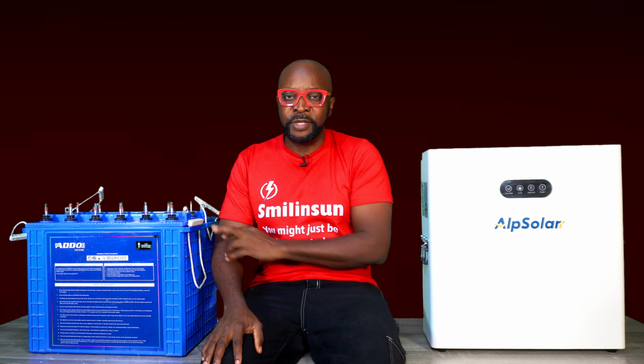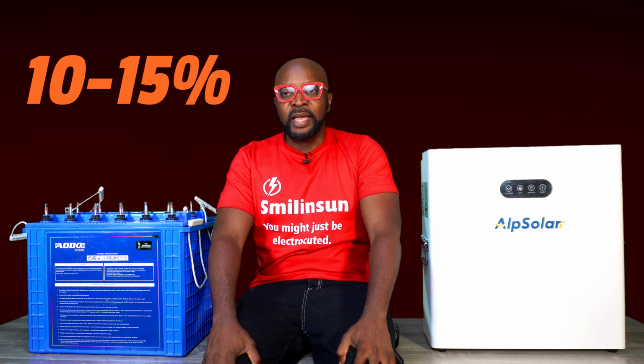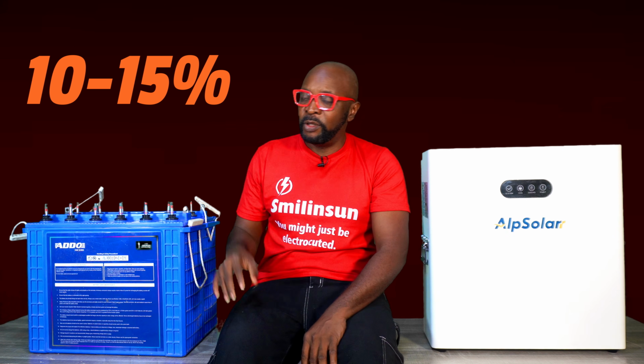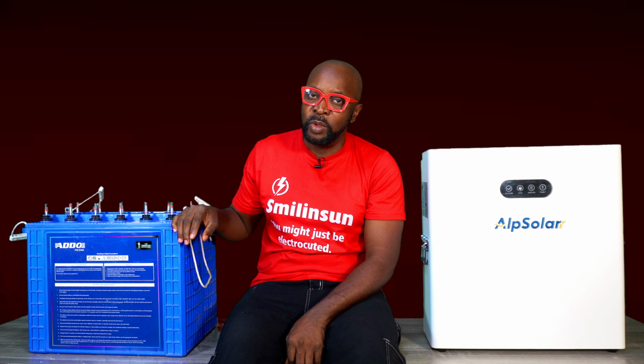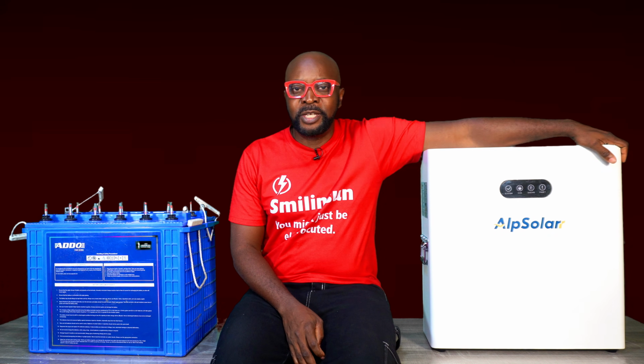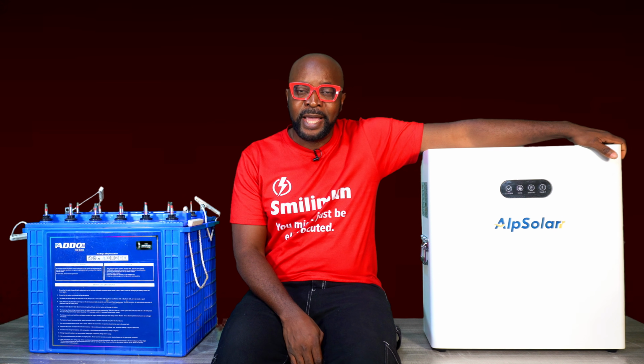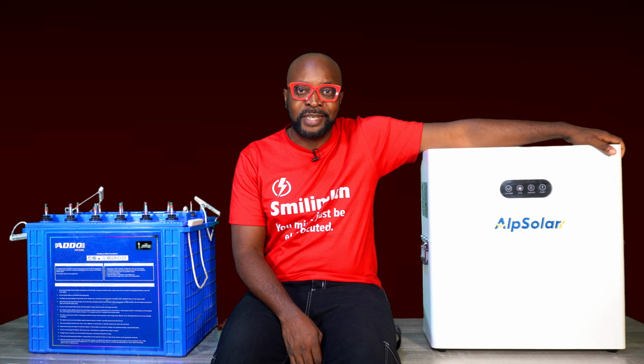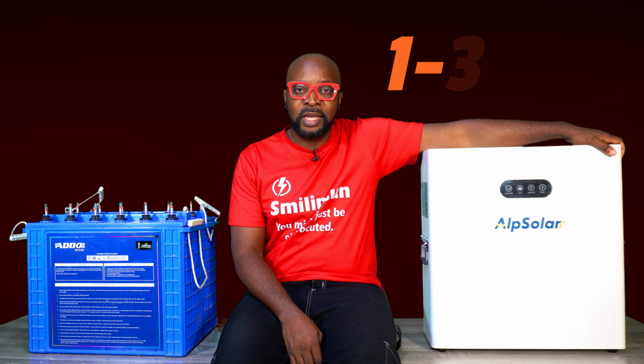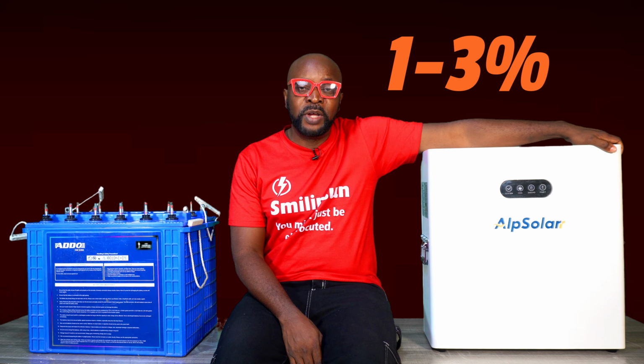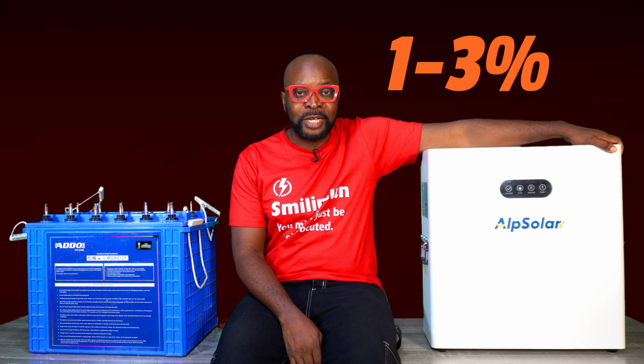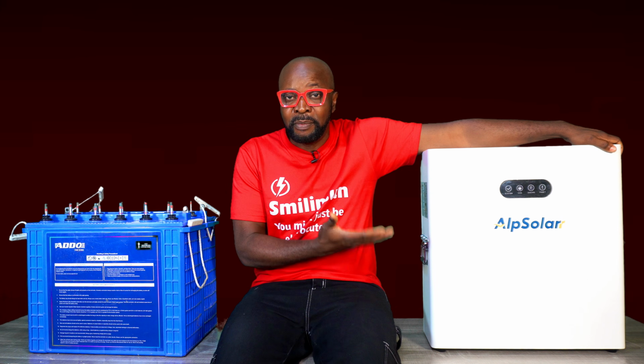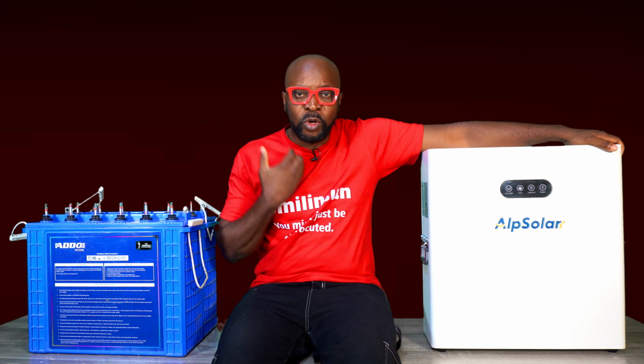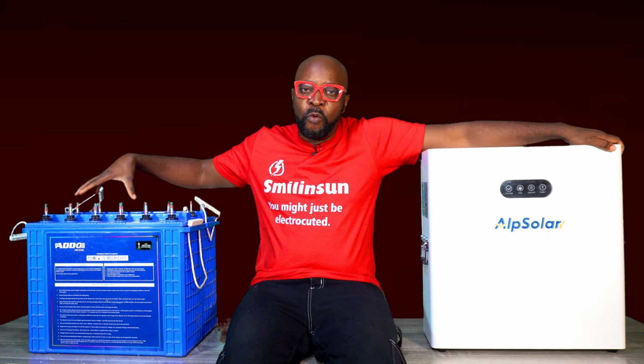So what's the self-discharge for each of these batteries? The self-discharge for the flooded lead acid battery, the tubular battery, is between 10 to 15% in every single month. That's why when you leave it for a very long time, it runs pretty low. But for the lithium battery, the self-discharge is quite negligible. It's actually very insignificant. It's between 1 to 3% in a month. So that means you can leave it for a very long time. And even if it does self-discharge to the point where it gets low, it doesn't affect the battery. So that's one of the very strong edges that it has over the tubular battery.